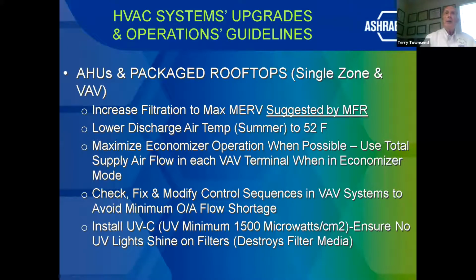Okay, for air handlers and package rooftop units, for single zone as well as variable air volume, increase the filtration to the maximum MERV that the manufacturer suggests that you can have. Lower the discharge air temperature in the summer, possibly to 52 degrees. Maximize economizer operation when possible. Use total supply airflow in each VAV terminal when in economizer mode. Fix or modify control sequence in VAV system to avoid minimum outside airflow shortage. And install UVC, preferably UVGI, that has a minimum 1500 microwatts per centimeter squared. Ensure that no UV lights shine on the filters because the UV lights destroy filter medium.